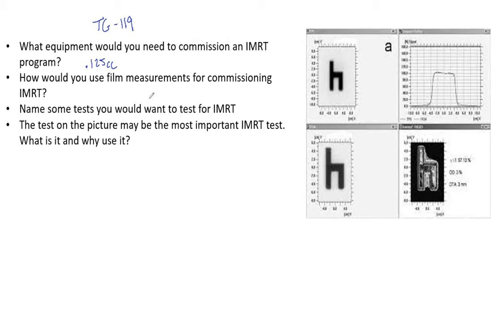If you put a film in the coronal plane and run tests, you can use gamma analysis to verify the agreement between what is being measured at the linear accelerator and the ideal dose plane from your treatment planning system. This uses distance to agreement and dose difference. Typically when we do patient-specific IMRT QA, we use this gamma analysis.